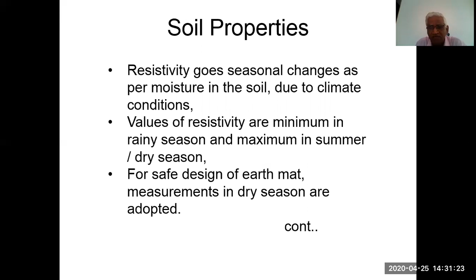Moisture in the soil is the most important element determining its conductivity, or resistivity. Conditions which increase or decrease the distribution of the moisture content in the soil result in corresponding changes. Resistivity undergoes seasonal changes as per the moisture in the soil due to climate conditions. Values of resistivity are a minimum in the rainy season and a maximum in summer and the dry season. For the safe design of the earth mat, measurements in the dry season are adopted.